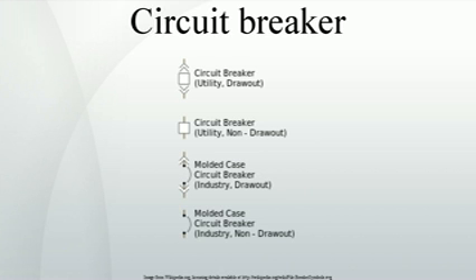MCCB, molded case circuit breaker, rated current up to 2500 A, thermal or thermal magnetic operation. Trip current may be adjustable in larger ratings. Low voltage power circuit breakers can be mounted in multi-tiers in low voltage switchboards or switchgear cabinets. The characteristics of low-voltage circuit breakers are given by international standards such as IEC 947. These circuit breakers are often installed in draw-out enclosures that allow removal and interchange without dismantling the switchgear.